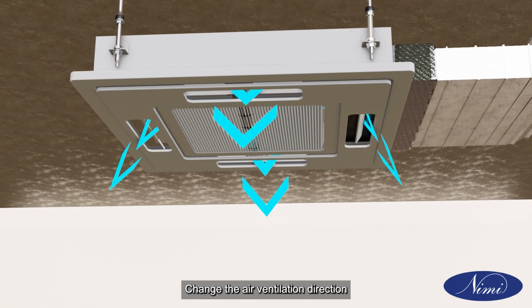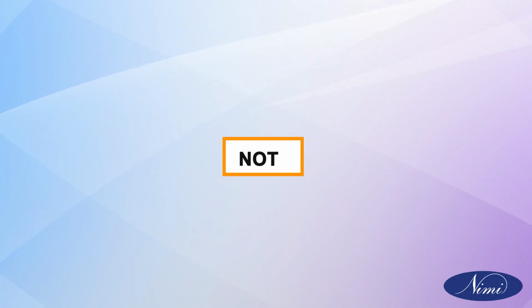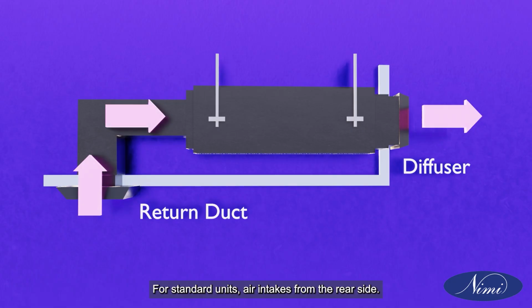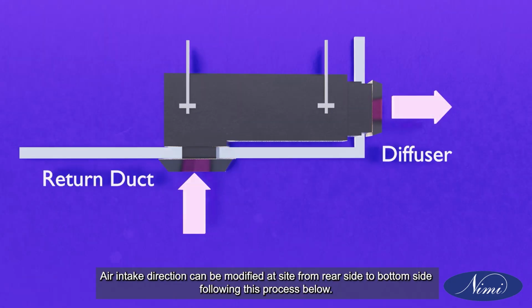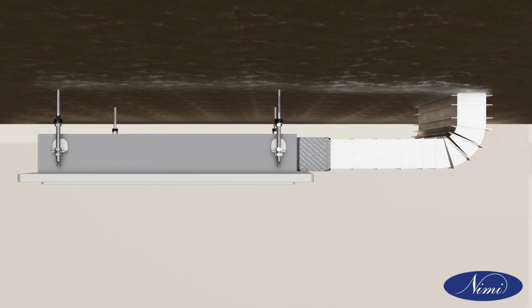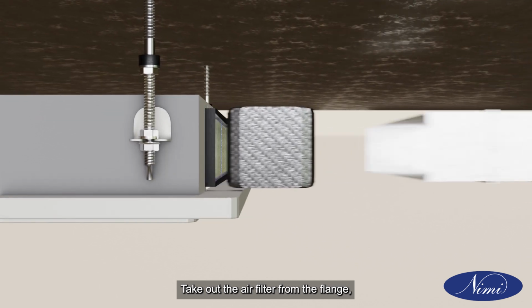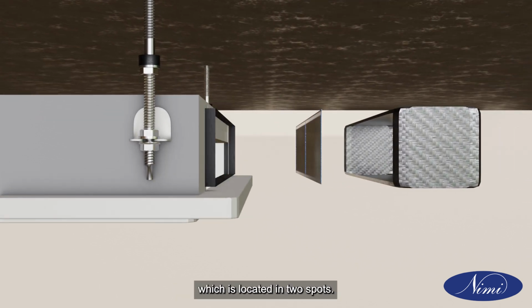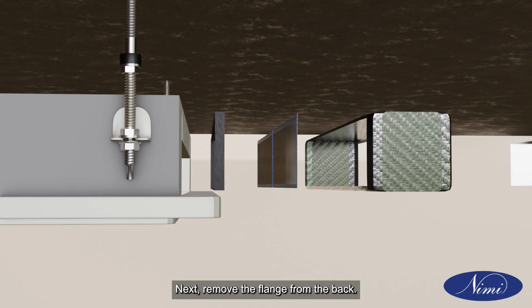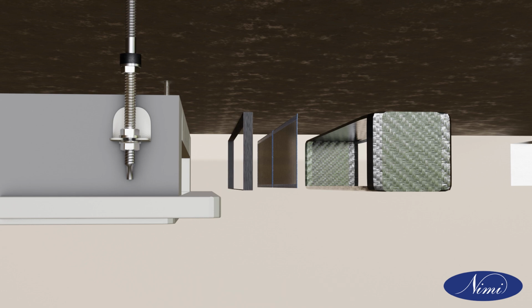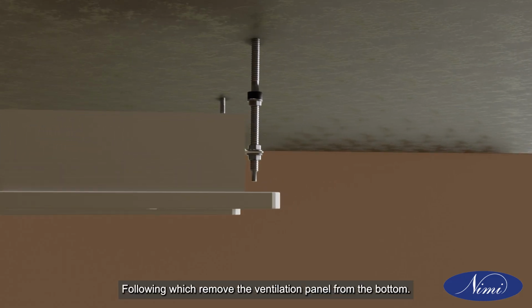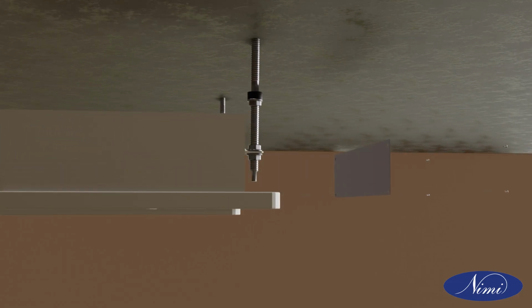Change the air ventilation direction. Note: for standard units, air intakes from the rear side. Air intake direction can be modified at site from rear side to bottom side following this process below. Take out the air filter from the flange, which is located in 2 spots. Next, remove the flange from the back. Following which, remove the ventilation panel from the bottom.